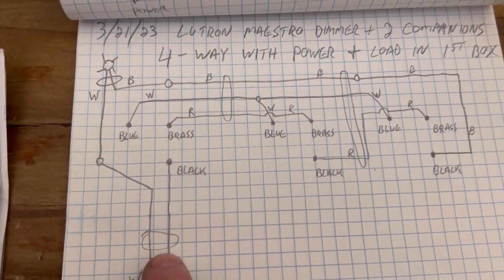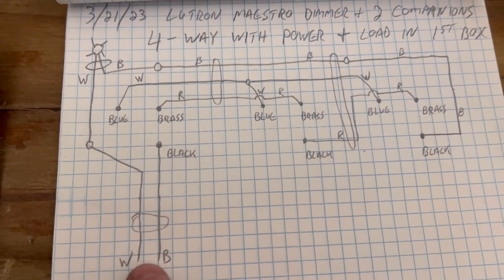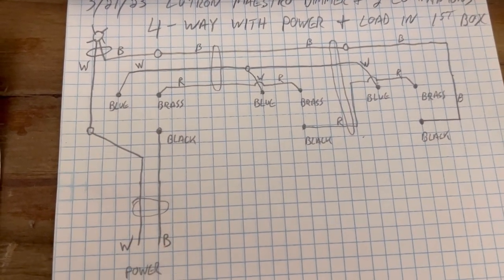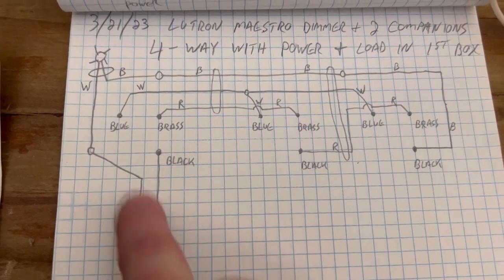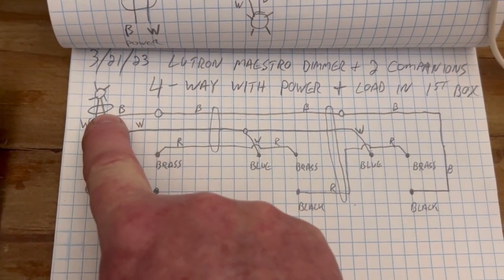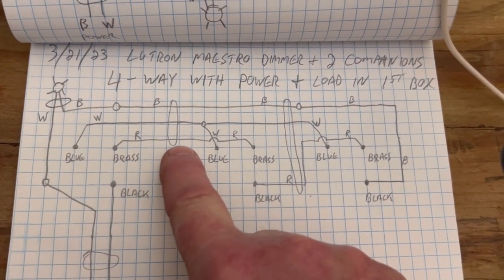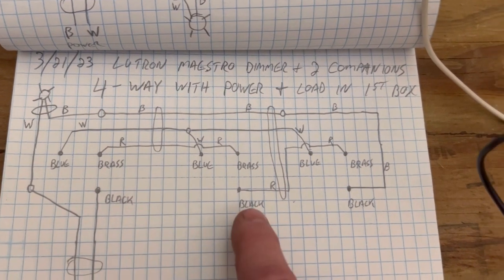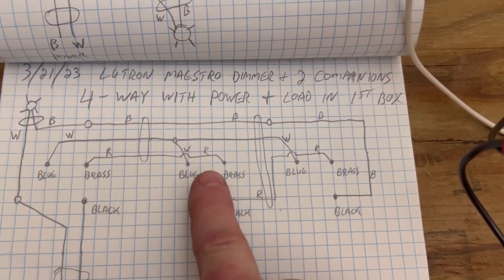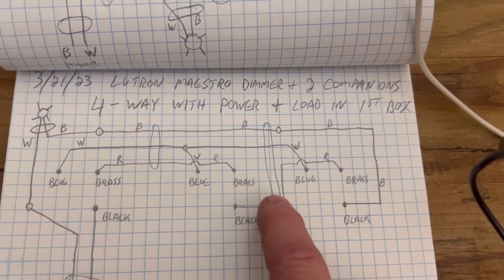These ovals are just representing a cable. So my power coming in is just a 12-2 cable. The cable that goes up to the light is a 12-2. The cable between the first switch and the second switch is a 12-3, and the cable between the second switch and the third switch is a 12-3.